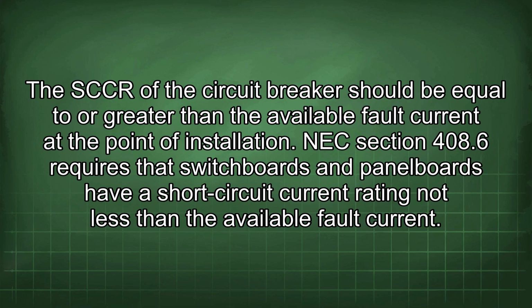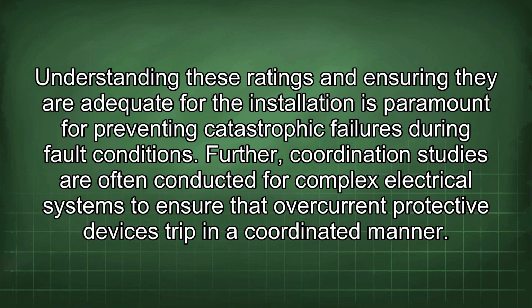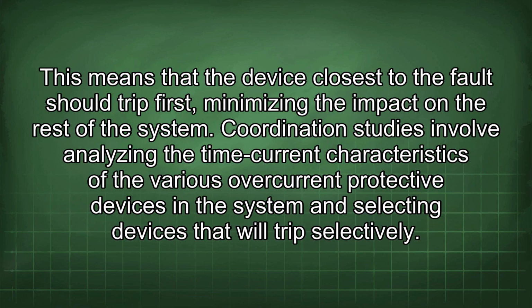Understanding these ratings and ensuring they are adequate for the installation is paramount for preventing catastrophic failures during fault conditions. Further, coordination studies are often conducted for complex electrical systems to ensure that overcurrent protective devices trip in a coordinated manner. This means that the device closest to the fault should trip first, minimizing the impact on the rest of the system. Coordination studies involve analyzing the time current characteristics of the various overcurrent protective devices in the system and selecting devices that will trip selectively.